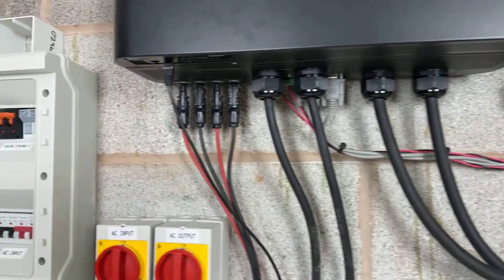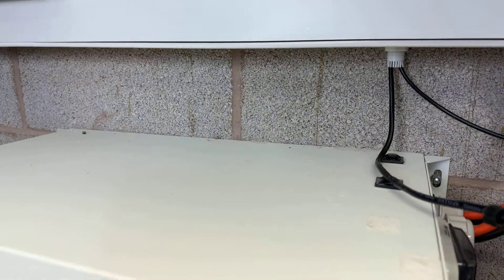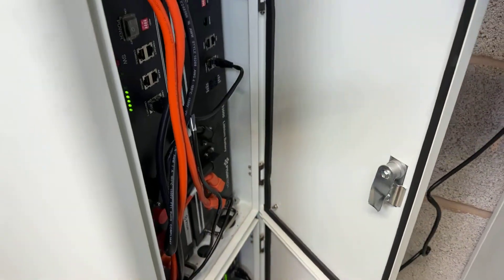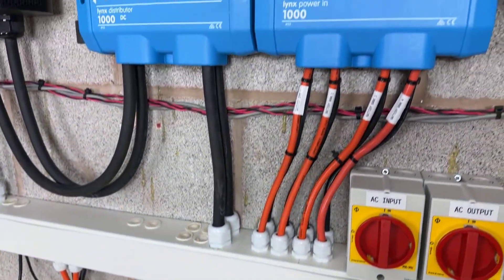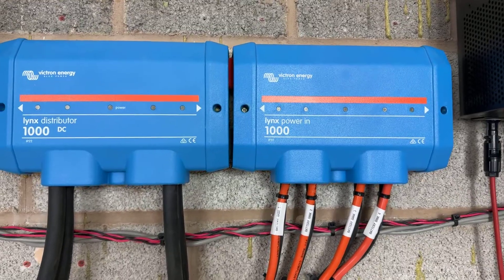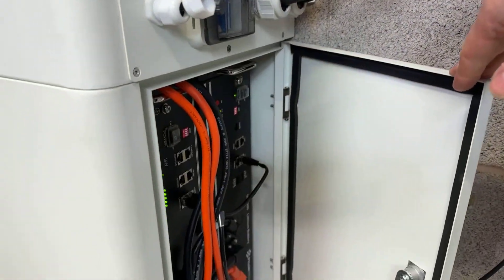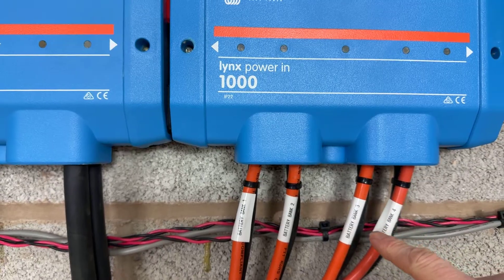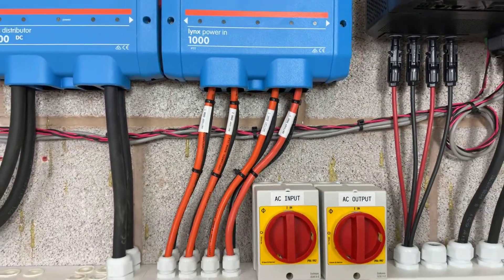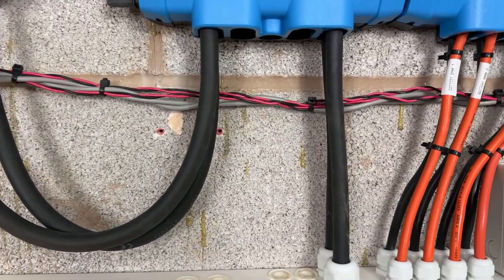Now that's done, we are ready to connect the batteries. The batteries are in parallel — we have eight units here, eight pylontech batteries, and another four, all connected in parallel using the Victron DC link bus bar. I have groups of two connected back to the Lynx Distributor, then another group of two, another one — four groups in total. It's better to share the current using 25 square millimetre cables.